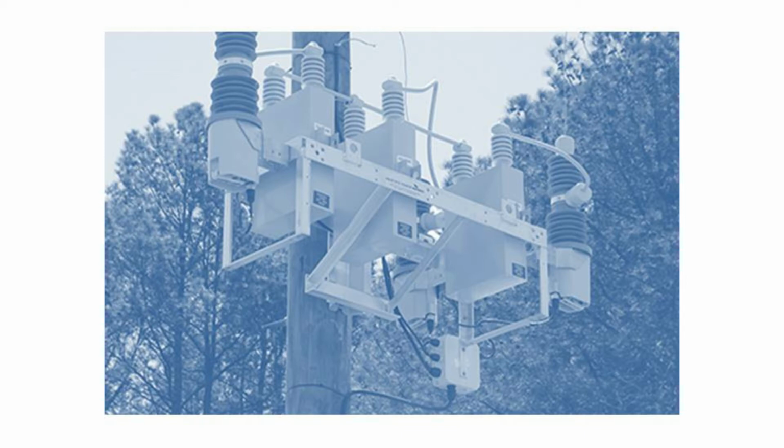The use of capacitor banks is to counteract inductive loading, such as motors, by increasing the current carrying capacity of the system. Now, I didn't mention that it helps adjust the power factor. The power factor is the ratio of real power, or power actually used, to the apparent power, or the power that is being supplied. By adjusting the power factor using a capacitor bank, you can increase the real power without increasing the apparent power.